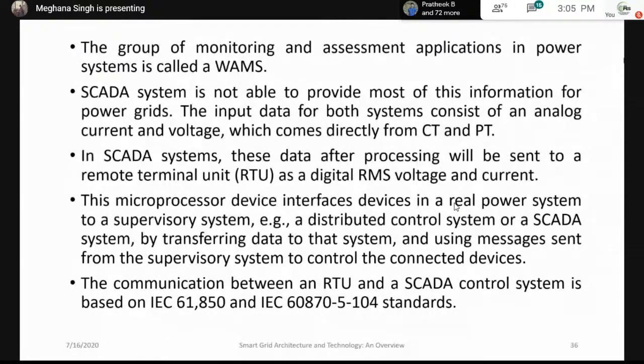Then this microprocessor device interfaces devices in real time for supervisory control. So you have the communication. The communication between the RTU and the SCADA control system is based on IEC 61850. IEC 61850 means International Electrotechnical Commission 61850. That's a standard which we use for intelligent electronic devices, IEDs. RTU to SCADA also uses the same concept. So a group of monitoring and assessment applications is WAMS. Next slide, please.